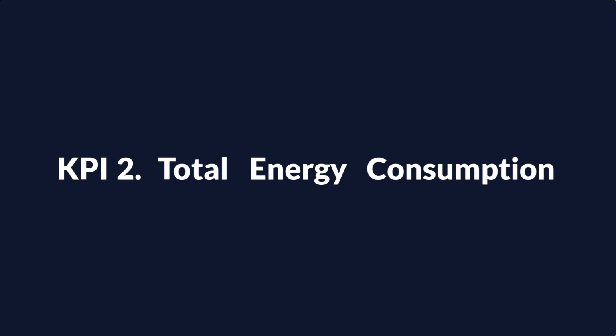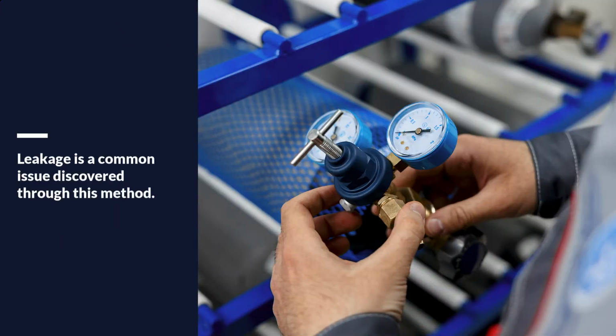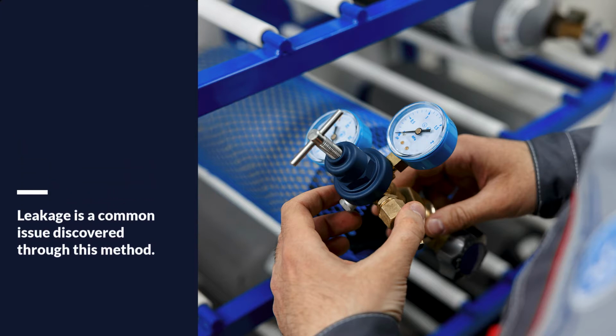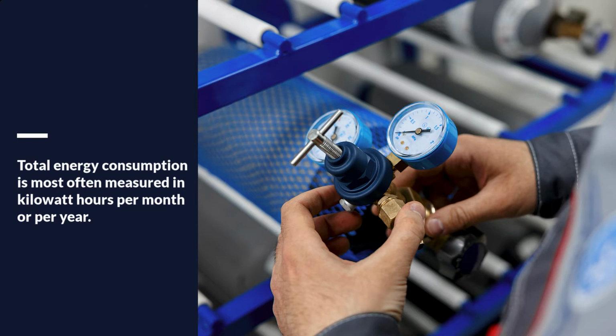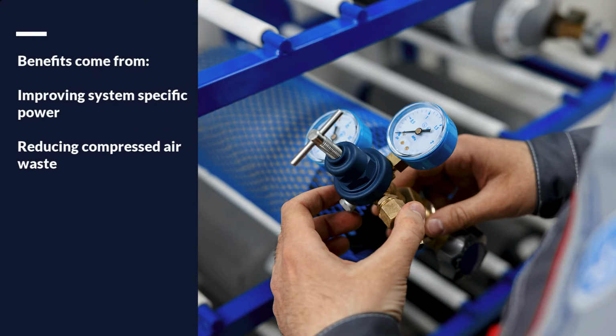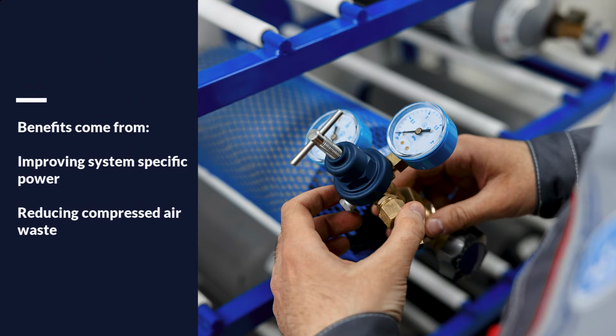KPI 2. Total energy consumption. It is possible to produce compressed air very efficiently, yet waste energy through leakage and inappropriate use of that air. Total energy consumption is a measure of how much total energy a compressed air system consumes over a specific measurement period. It is most often measured in kilowatt hours per month or per year. Improvements to this measure are gained by improving the system-specific power and/or reducing compressed air waste.